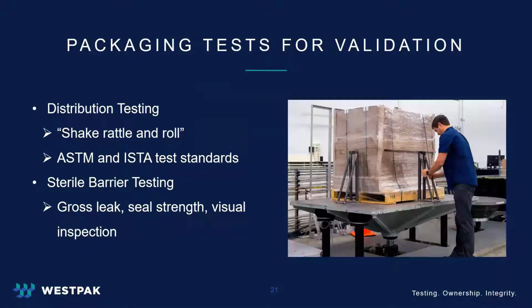There are many test methods that may be involved in a medical device package validation, which can be categorized into two groups. The first is distribution testing, which many people refer to as shake, rattle, and roll testing. Distribution testing will simulate hazards seen in the shipping environment. This can be considered the time a package system travels from the manufacturer to the end user or patient. The type of hazards seen during this process are inputs like drop, vibration from vehicles, as well as compression due to stacking. ISTA 3A and ASTM D4169 are good representations of the standards used to simulate distribution.